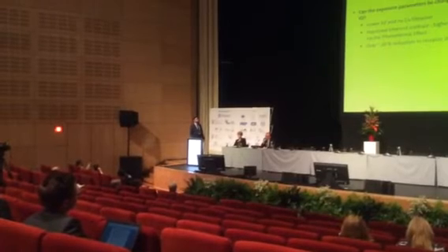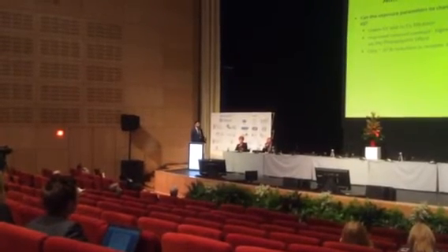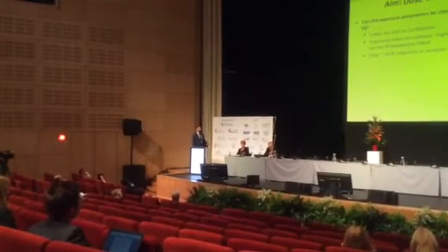So the first question I had to answer was, can the exposure parameters be changed to result in an improved image quality? Well, we've seen that removing the copper filtration, lowering the kV, you're lowering the beam quality and therefore improving the inherent contrast in the image, because a higher proportion of the interactions occur via the photoelectric effect. And the white paper suggests that this improvement in image quality and the contrast is not associated with an increase in the noise, because the receptor dose only actually decreases by 10% when dropping down from 57 kV to 40 kV.